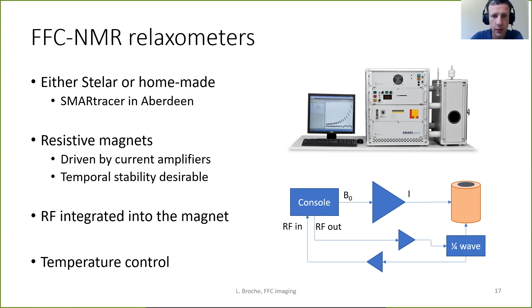Of course, the practice is always more difficult than theory. For this kind of system, you have a lot of things to take into account to make sure that the system can cope with a lot of problems, temperature fluctuations, stability, and so on. These systems use resistive magnets, and because they use resistive magnets, they need large currents that need to be controlled quite accurately. Again, you need radio frequencies, and in the system that we have, which is a Smartracer, similar to what you see on the picture here, there is a temperature controller, which is also very interesting for material science. Now, if you want to scale that into an imager, you have a few major differences.